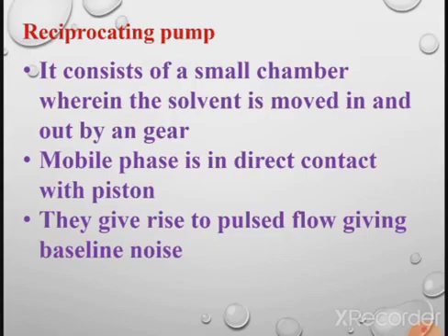Due to the to and fro direction of the piston, the mobile phase is compressed and released, and this gives rise to a pulsated flow, so baseline noise may occur. Also, in this reciprocating pump, the mobile phase is in direct contact with the piston, and that's why it may cause corrosion or contamination.